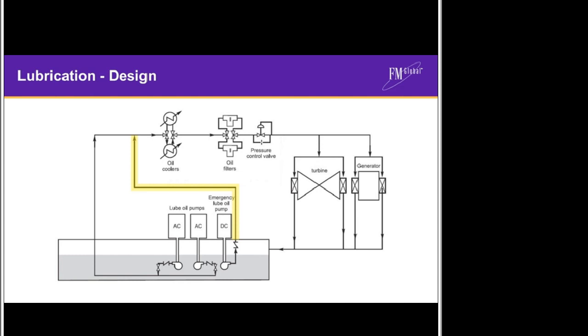The challenge with this is that it introduces a single point of failure. If the coolers are blocked or the filters are blocked, when the pressure drops on the lube oil system, the emergency lube oil pump will start and it will try to feed lube oil through the same blockage that the AC pumps were feeding, potentially leading to a failure of lubrication on the turbine. FM Global recommends to its clients that the emergency lube oil supply is directed onto the bearings, bypassing oil coolers and filters to ensure that no such single point of failure exists.